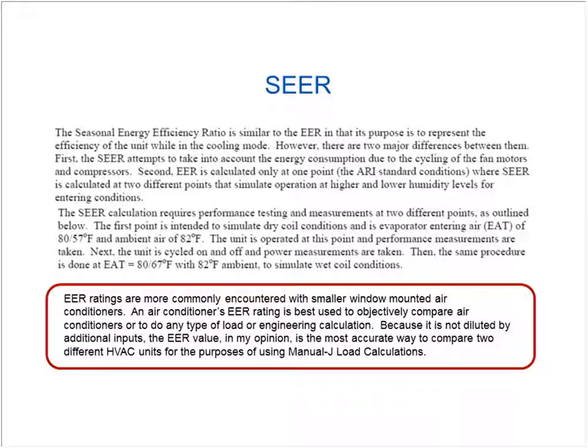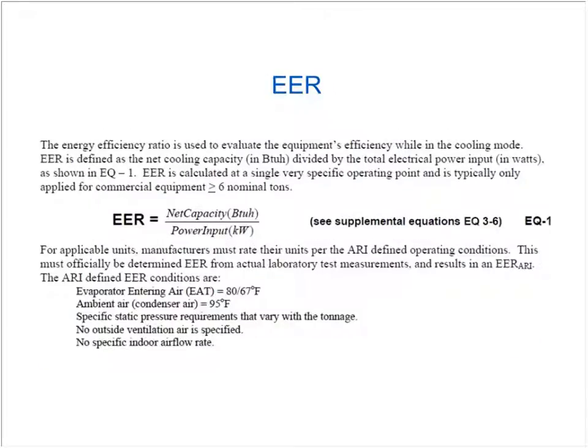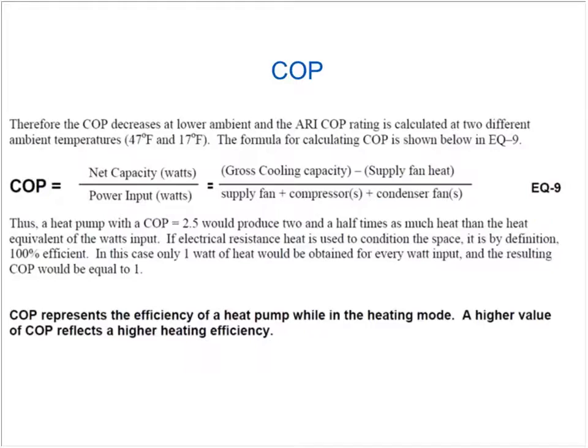So having said all that, it's really just kind of a benchmarking system for ductless heat pumps to give a value to them. And we're going to talk more about why that's good and bad in a minute. But then there's also the EER, the energy efficiency ratio, which is just more funky math that not many people are paying much attention to today in the building, because it doesn't represent any rebate values. But HSPF and SEER values are all indicative of rebate values. The other acronym that we'll talk about is COPs, the coefficient of performance.